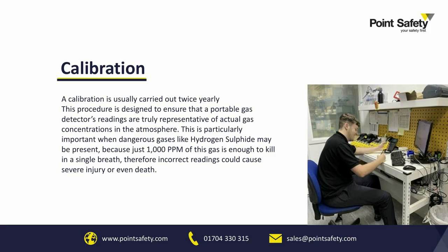Secondly, one of the most important parts of the process is regular calibration of the instruments. Normally, manufacturer recommendations are a minimum of 6 months, although depending on the area that you are working in, the environmental conditions, and the background gases in that area, you may deem that this needs to be carried out more regularly. Again, the results that you're getting from the calibrations will show if there's been any drift on your sensors, particularly the flammables. So it's important to carry this out on a regular basis.